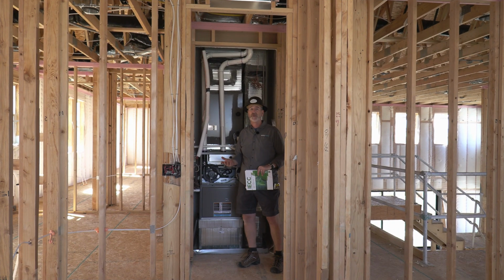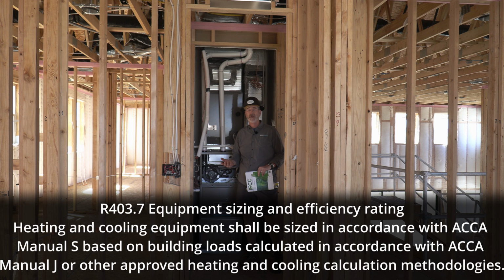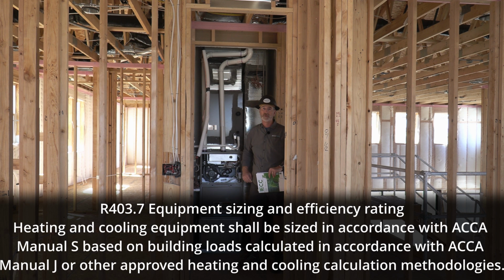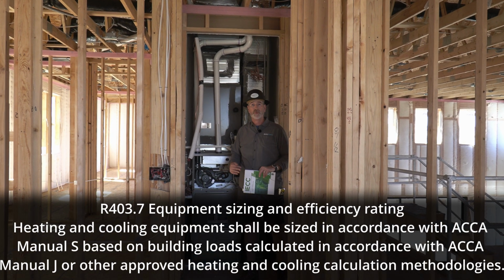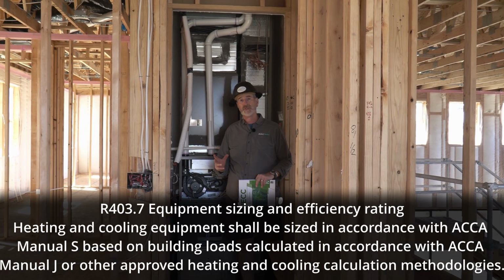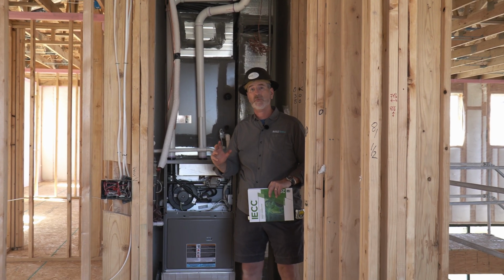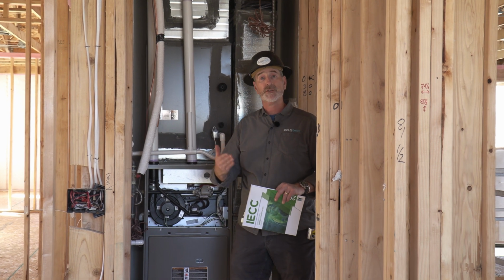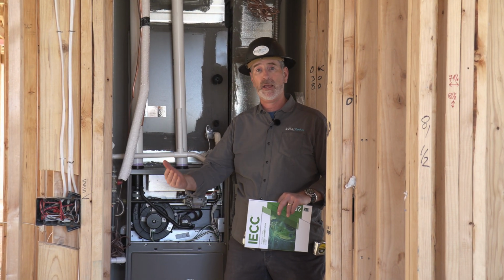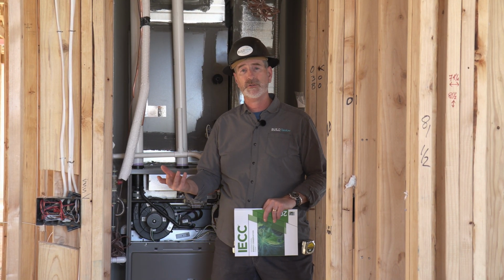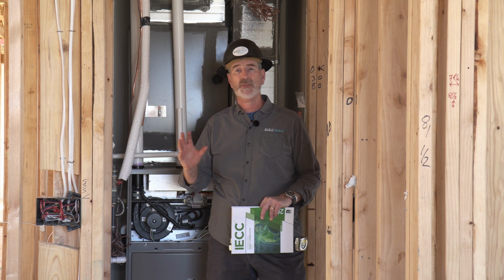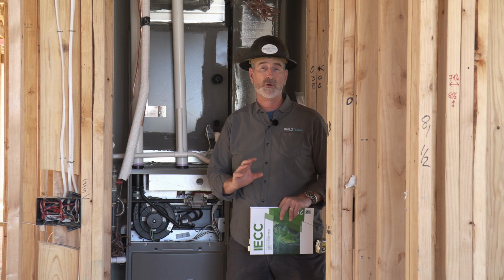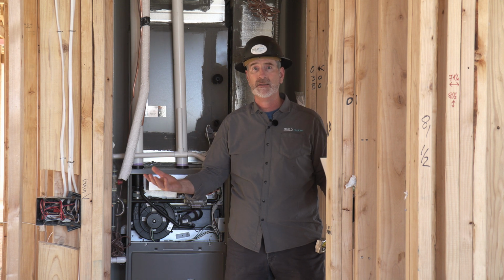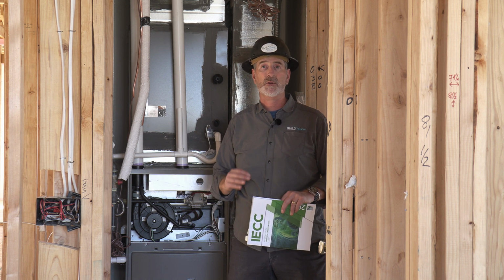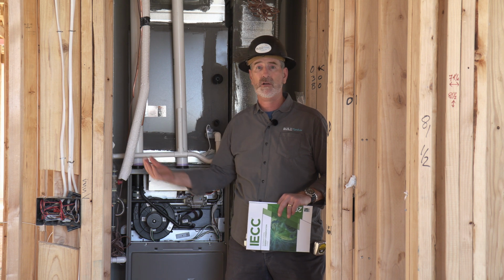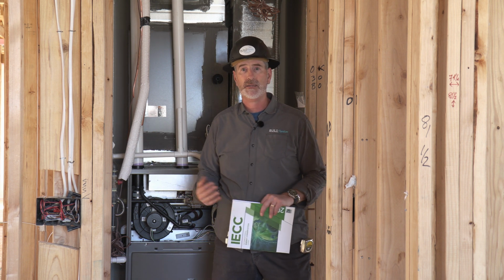Section R403.7 of the Energy Code says that our equipment needs to be properly sized before we install it. There are a couple issues with that. The first thing is that when we do, we're required to do a Manual J and a Manual S, and we're not necessarily required to do a Manual D. But when we do that HVAC design work, we have not yet built the house. So we're proposing to install the right insulation and have the right air tightness and whatnot.